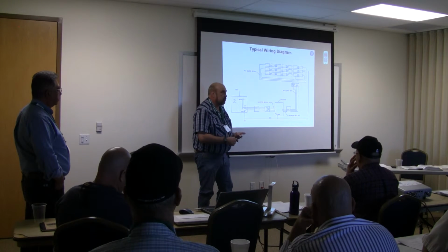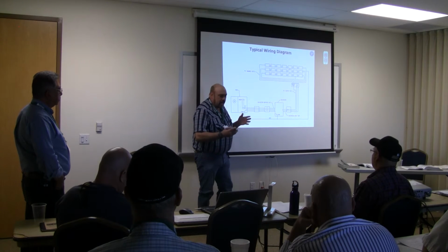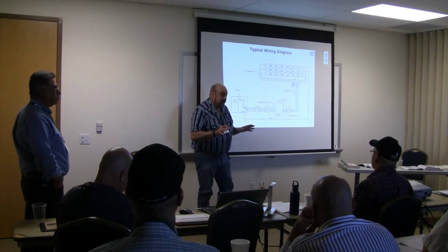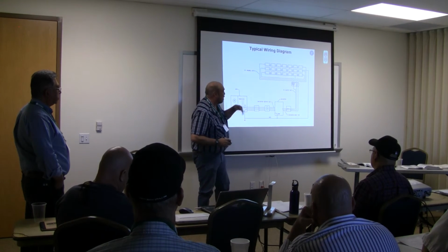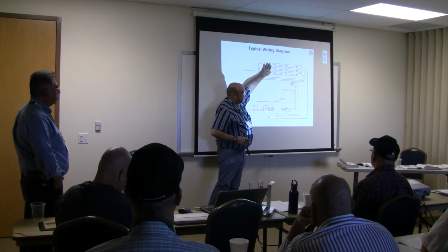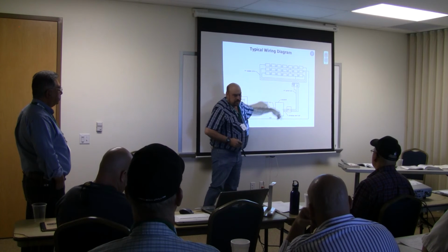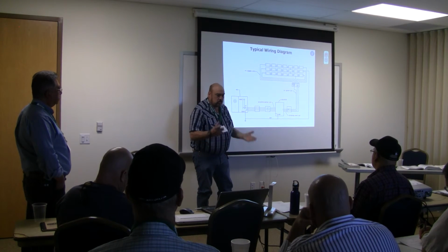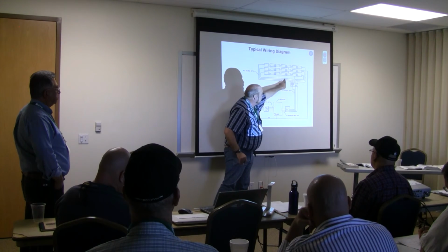Okay, you're going to be using 310.15(B)(3)(c), 310.15(B)(2)(a), and I think (B)(2)(c). For the area, always remember, for the area that you're in, you've got to find out the highest ambient temperature. Now we're talking high ambient temperature here, we're not talking about the lowest, because the lowest only affects the module itself. Now we're talking about high ambient temperature.